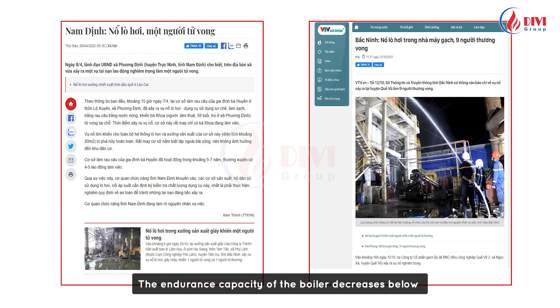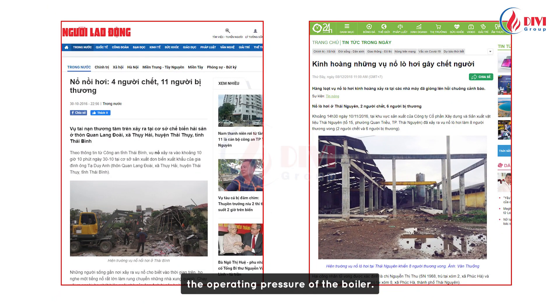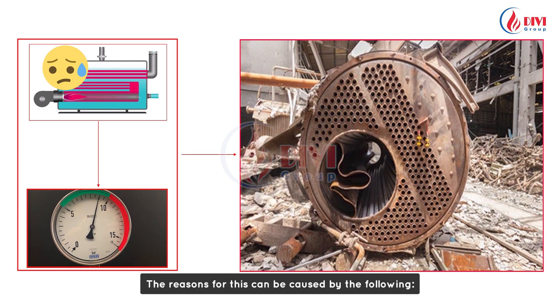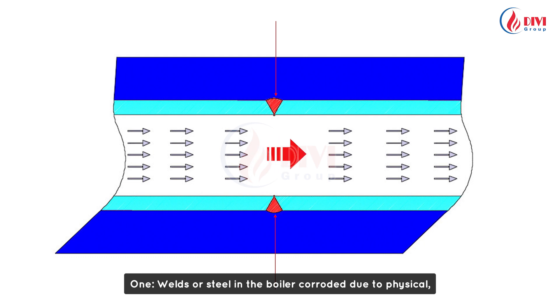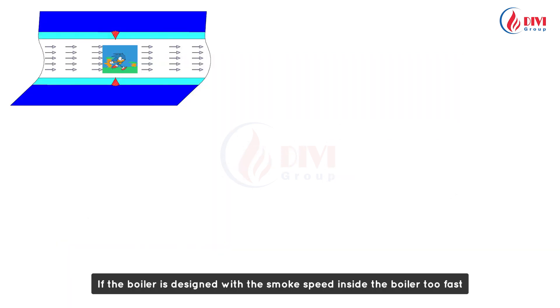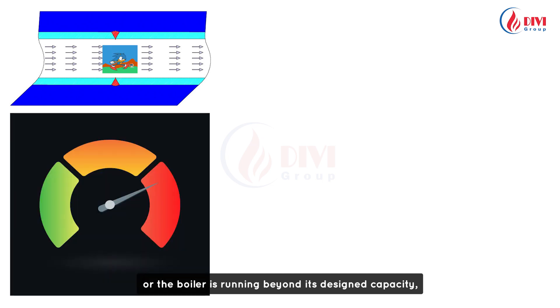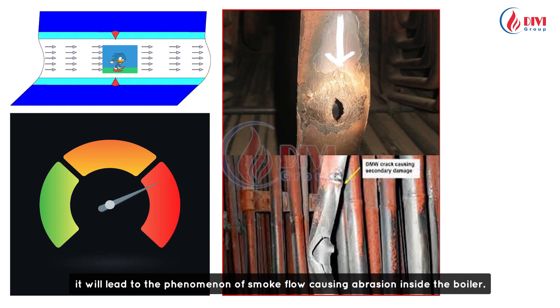For the second reason, the endurance capacity of the boiler decreases below the operating pressure. This can be caused by several factors. First, welds or steel in the boiler corrode due to physical or mechanical abrasion by the smoke flow inside the boiler. If the boiler is designed with smoke speed that is too fast, or the boiler is running beyond its design capacity, it will lead to the smoke flow causing abrasion inside the boiler.